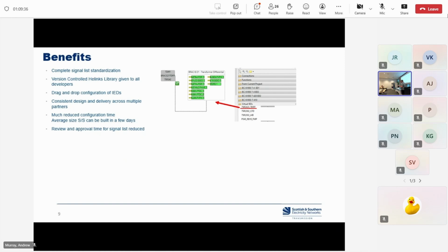They'll maybe only allow you to import or export a CID file, and won't allow import of ICD files. The only way around that is falling back to an Excel import sheet per device. We can't add it to the library, but we can have a spreadsheet that's still controlled in that way. One example is the MiCOM C264 BCU, where you can't put an ICD file into the device, you can only get a CID file from it.